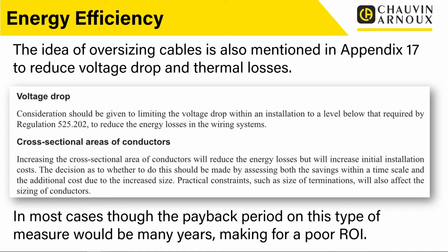So often the price of that additional copper, to actually make the cables bigger, when you look at it, is for very small savings. They are real savings, but it is very small savings. You would need that copper to be there for a long period of time. You would need a long life of the electrical installation before you would start actually making returns on investment.